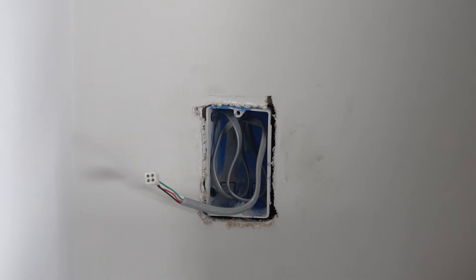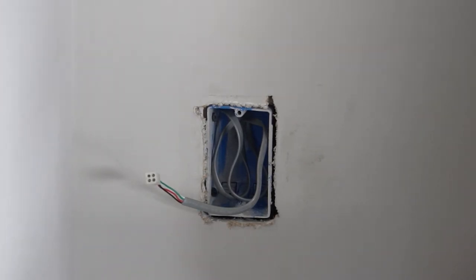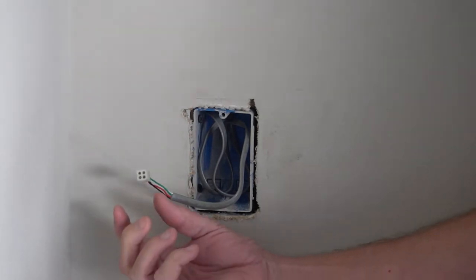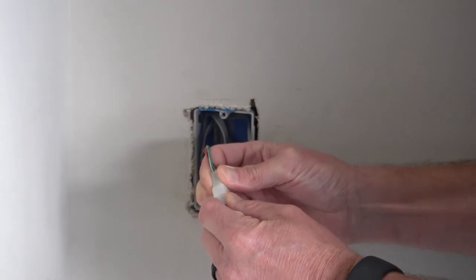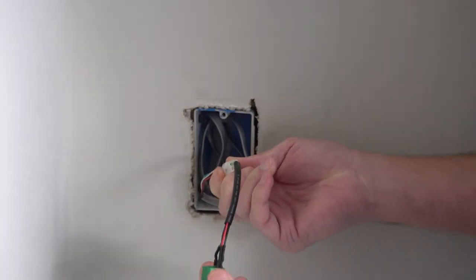Install the key switch controller in a single gang box. Mount it in an area that will be visible from the lowered cart assembly. Run the control wire from the motor drive assembly control board to the key switch controller.